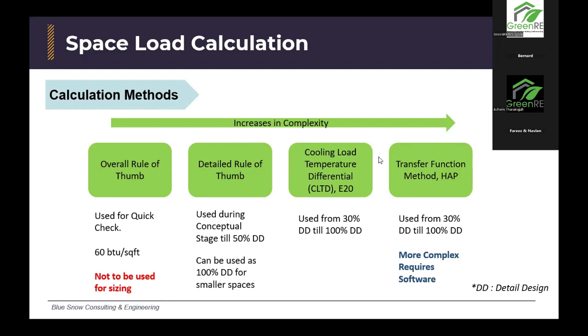So the purpose of having the other two methods is that in the end, you're able to optimize your size. You don't want to oversize your system. And on top of that, you will be able to know your load profile. Knowing your load profile, you'll be able to do things like load staging, like how well you manage your load. For example, hotels may not always run at their full capacity. And if you only size your system with the mindset of running at full capacity, systems may not run efficiently at part load if they are not designed well to handle their designated part load. So that's something to keep in mind.